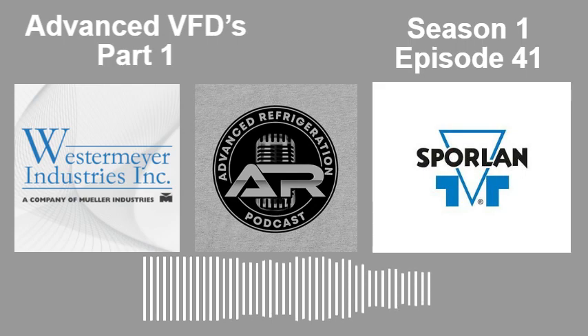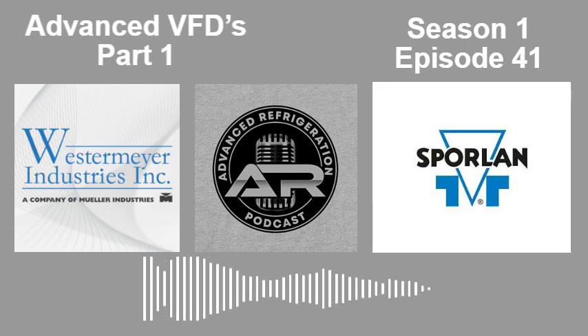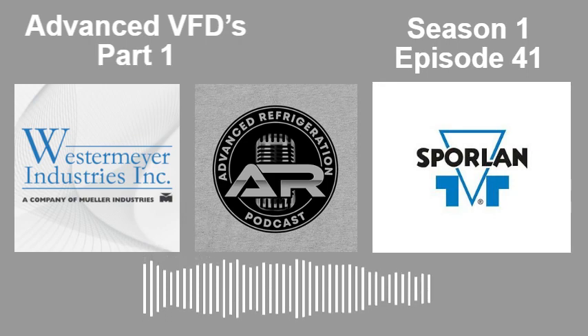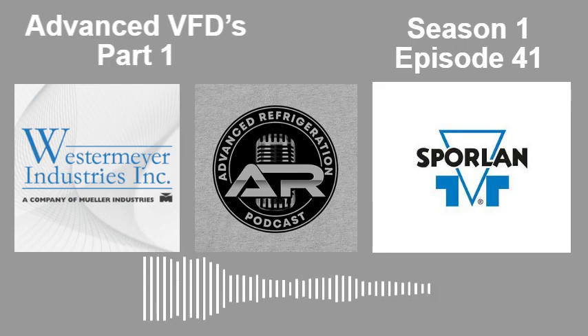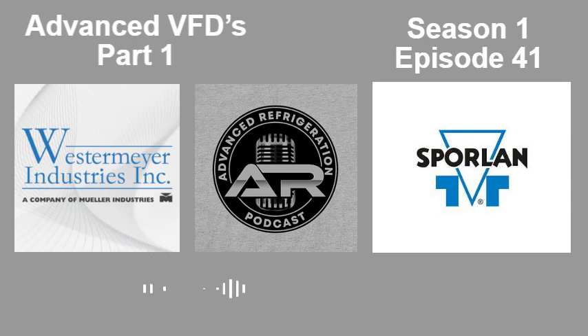When I have comm issues and we're splitting the network, you start at the beginning and get a couple boards on, so you know the E2 or the controller is not the problem. I split it off from there and plug the first 2 boards in. If I get them online, I just keep going. Then I may jump 5 boards and bite off a bunch, unplug the rest of the network, and if I get those 5 boards on, okay, I keep moving down the line. But if I don't know where to go on the line, we have a huge problem. I'm going to spend a bunch of time tracing out where this comm loop is going. That's why labeling your wires and actually following the print is a great thing.